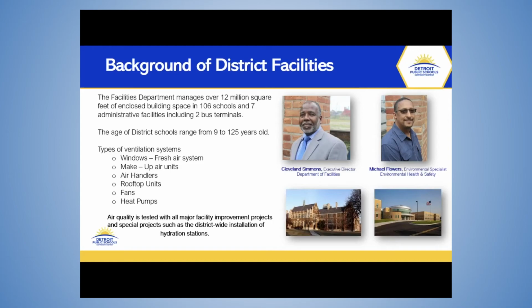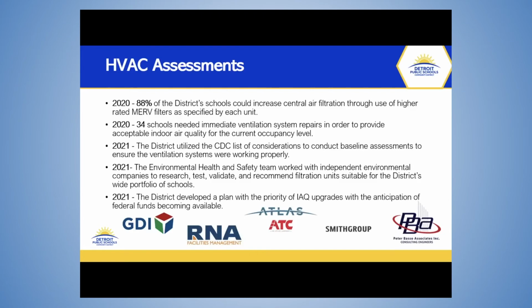On the bottom slide here, it just shows the different types of ventilation systems that the district utilizes. All right, what's going well in Detroit? So we conducted HVAC assessments back in 2020 up until 21. Through that assessment, we found 88% of our buildings could increase central air filtration through the use of higher rated MERV filters. 34 schools needed immediate ventilation system repairs, and the district developed a plan with priorities to upgrade these buildings with federal funds that were becoming available.